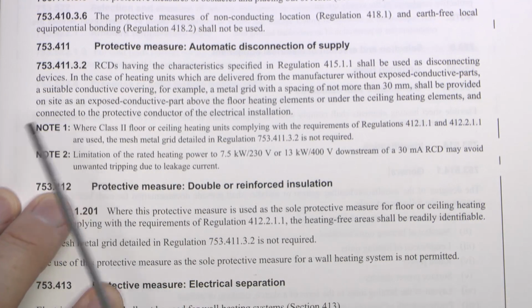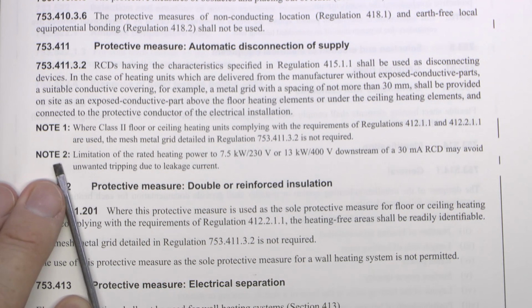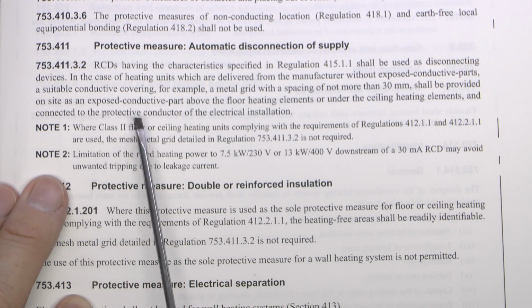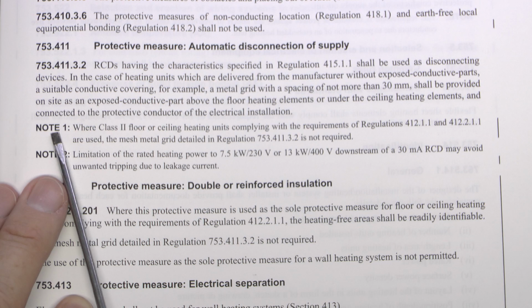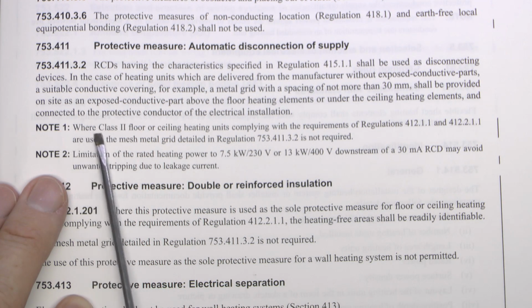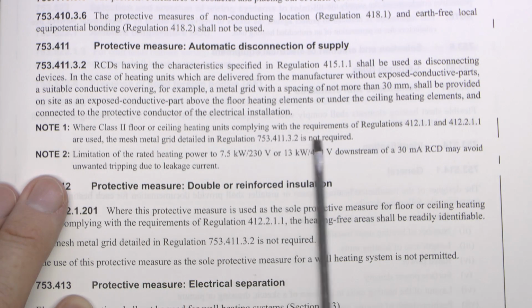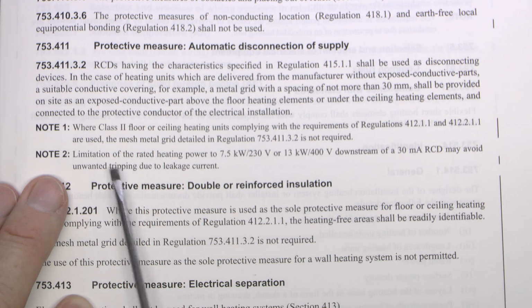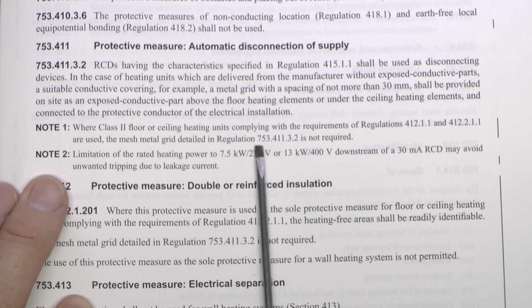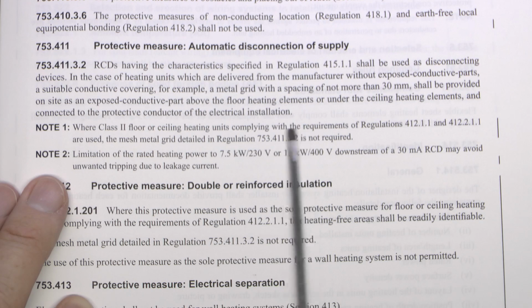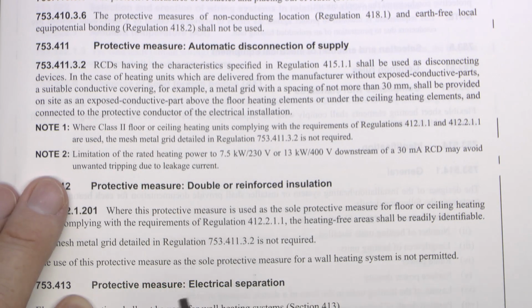Now for the section here, 753411, we've actually got a note 2 here, which was previously included, but that was actually note 1, and note 1 has been added. And we've got there, where class 2 floor or ceiling heating units complying with the requirements of these regulations are used, the metal mesh grid detailed in this regulation is not required. So that's added in, and the other note has just moved down and been renumbered.